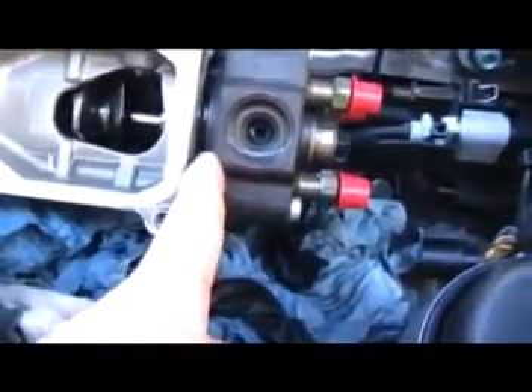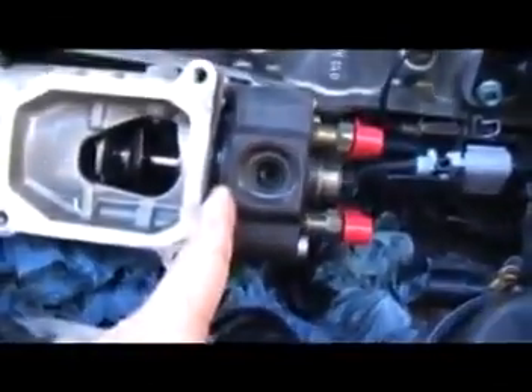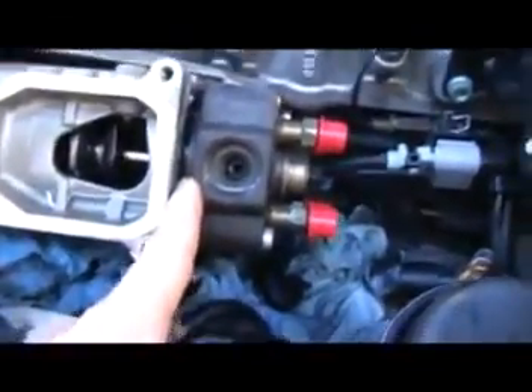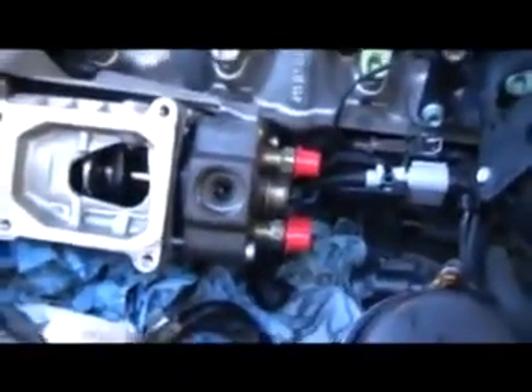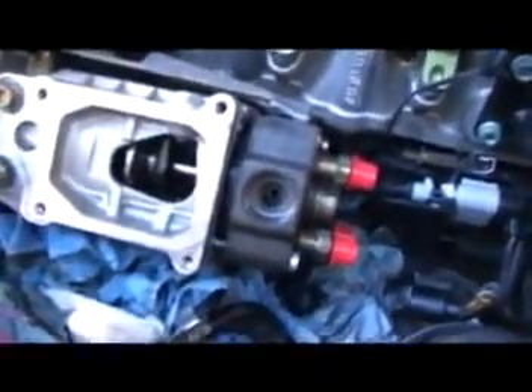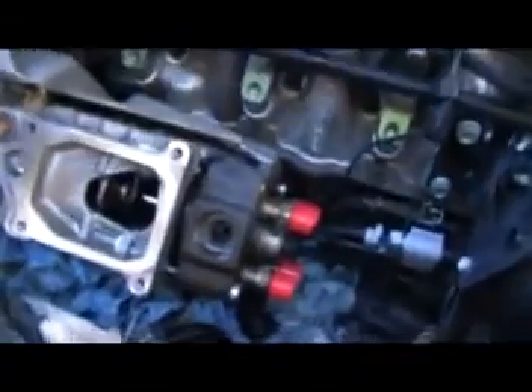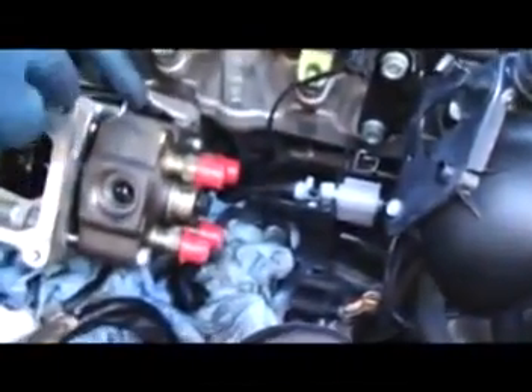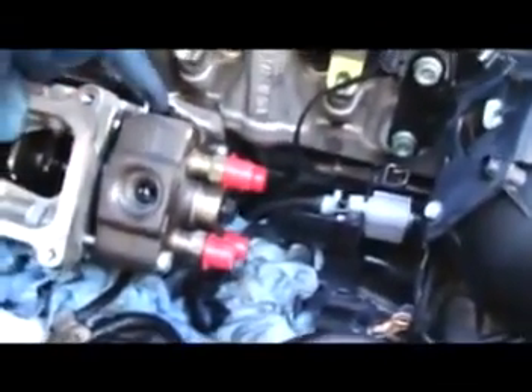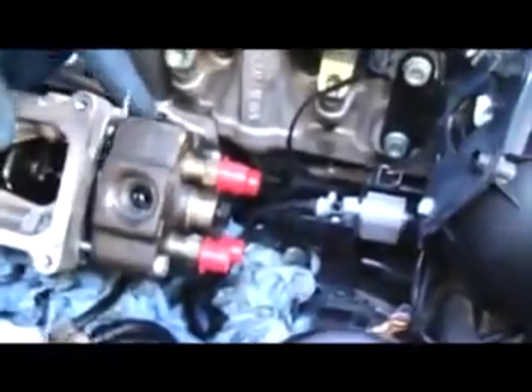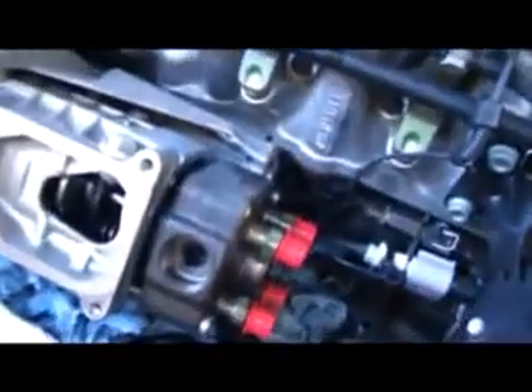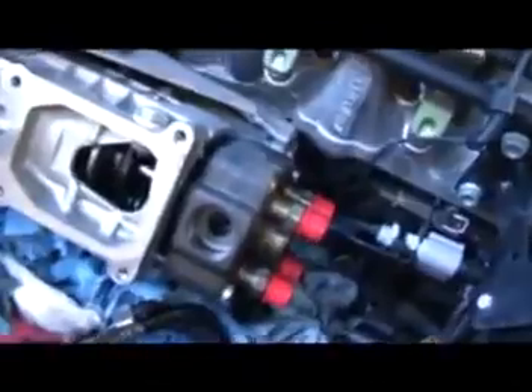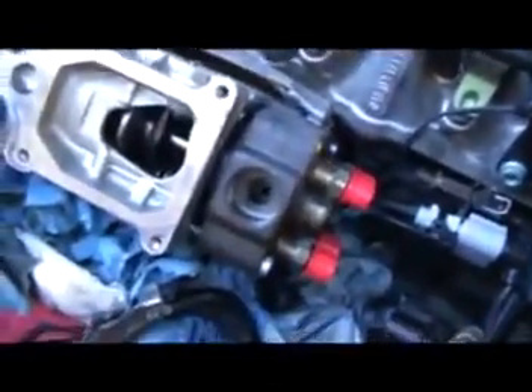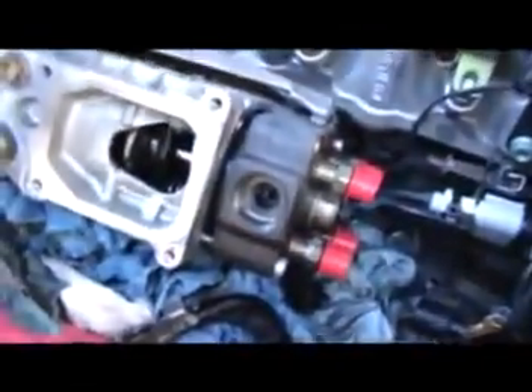So you can see the O-ring right in there, and most of the time with an old pump, it's going to be hard as a rock, or really, really stiff. So we're going to get a hooked pick, and we're going to carefully hook that O-ring with our hooked pick and dig it out of the groove without scratching the groove. I've got to bring my other pick. You have a curved pick? I have this.